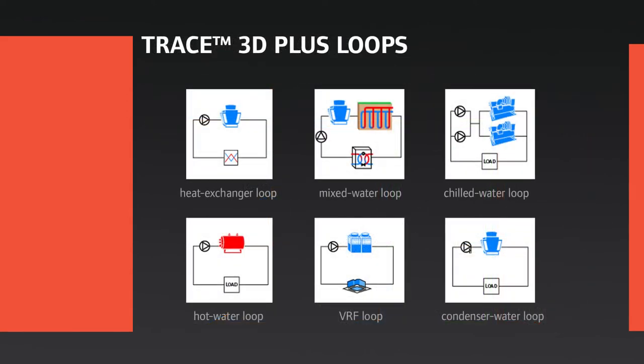There are six different types of loops selectable in TRACE 3D+: heat exchanger loops allow you to transfer loads between loops; a mixed water loop is the condenser loop from a water source heat pump system, typically including a boiler and a cooling tower; a chilled water loop has chillers; and a hot water loop has heating equipment such as a boiler. VRF is unique in that the loop being modeled is a refrigerant loop, with the plant housing unloading curves for the condensing equipment. Finally, condenser water loops reject energy from a building to heat rejection equipment such as a cooling tower.